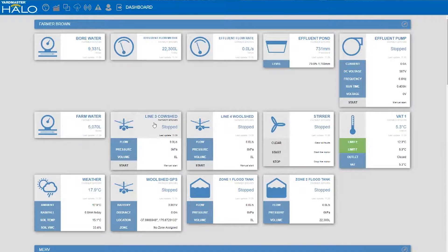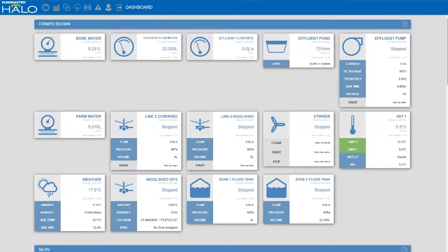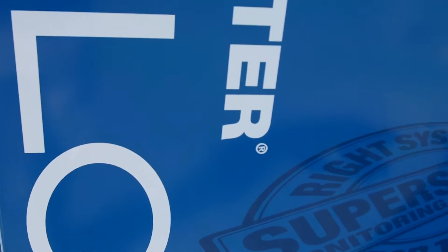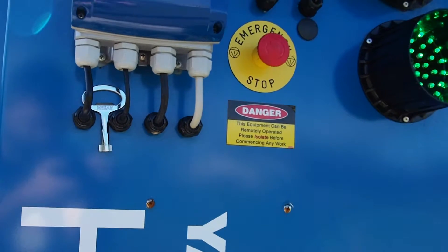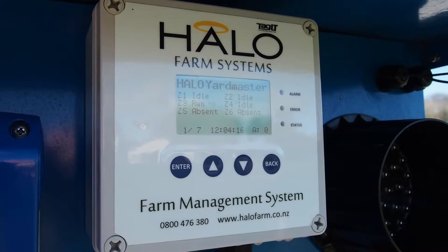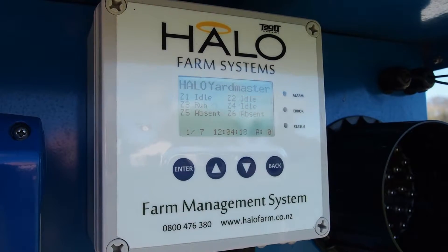With the system it can do multiple duties. With this irrigation line here you might be going for 7 litres a second, but on the other side of the farm you might only desire 6 litres a second. You can set up your irrigation line to whatever flow rate you desire, or you can set it up so it's driven by pressure — the VSD will ramp up and down to adjust the pump speed.